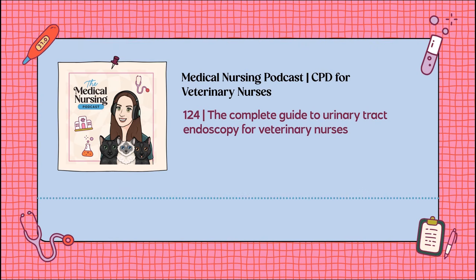So what we want to do for that quick patient-side clean is suction or flush some pH neutral enzymatic cleaning solution through the channels and then brush through them as well. And then you can safely set the kit aside somewhere that it's not going to get knocked or damaged or anything like that, giving you a bit more time to do all those other things before that full clean is performed. And that full clean is exactly the same as we discussed for our rhinoscope and our bronchoscope in the last two episodes 122 and 123.